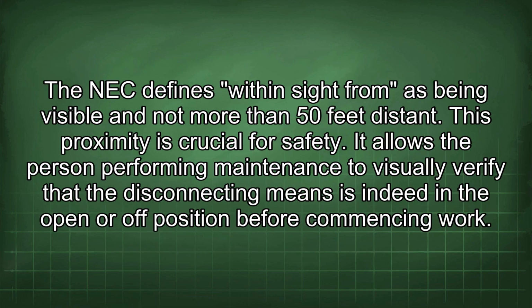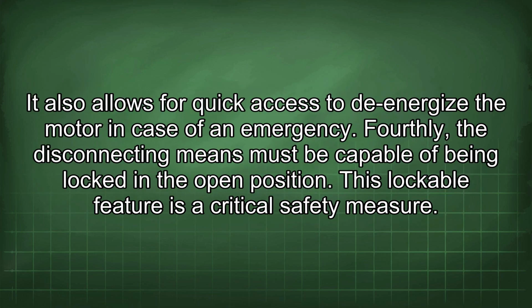Thirdly, the disconnecting means must be within sight of the motor. The NEC defines within sight from as being visible and not more than 50 feet distant. This proximity is crucial for safety. It allows the person performing maintenance to visually verify that the disconnecting means is indeed in the open or off position before commencing work. It also allows for quick access to de-energize the motor in case of an emergency.